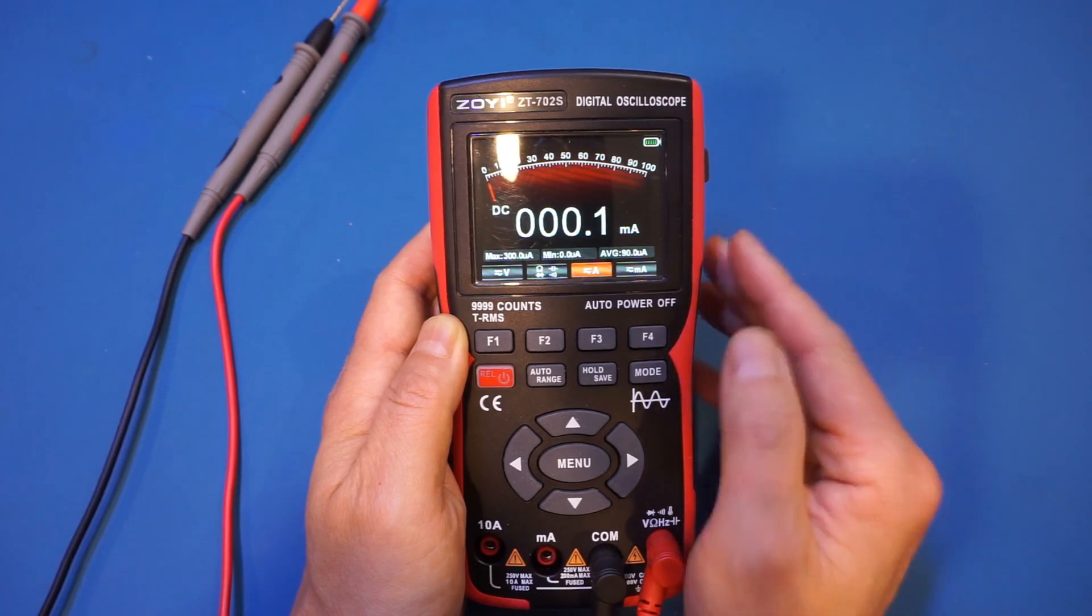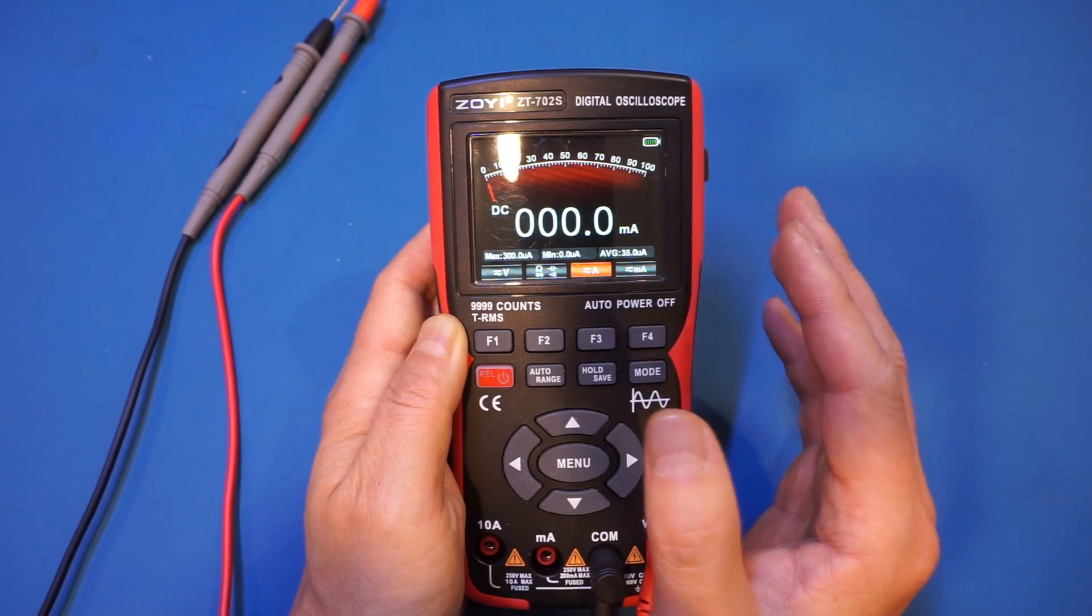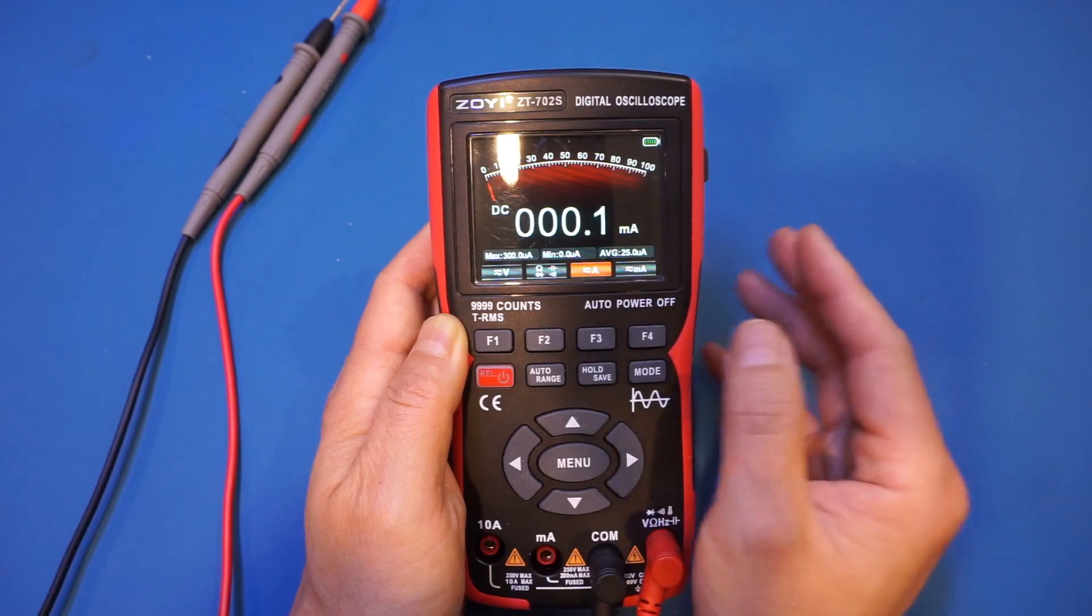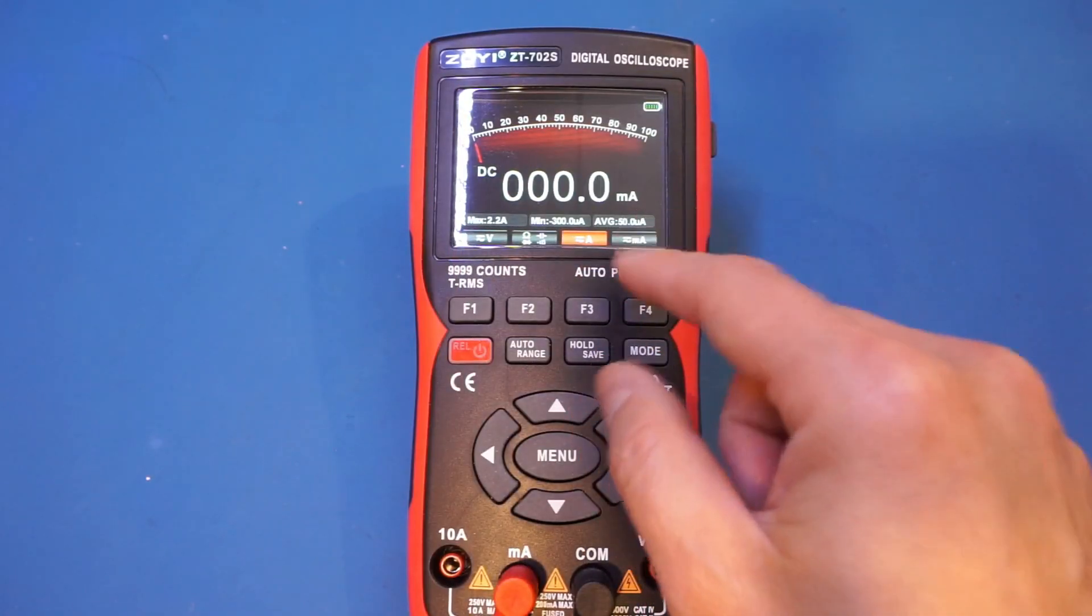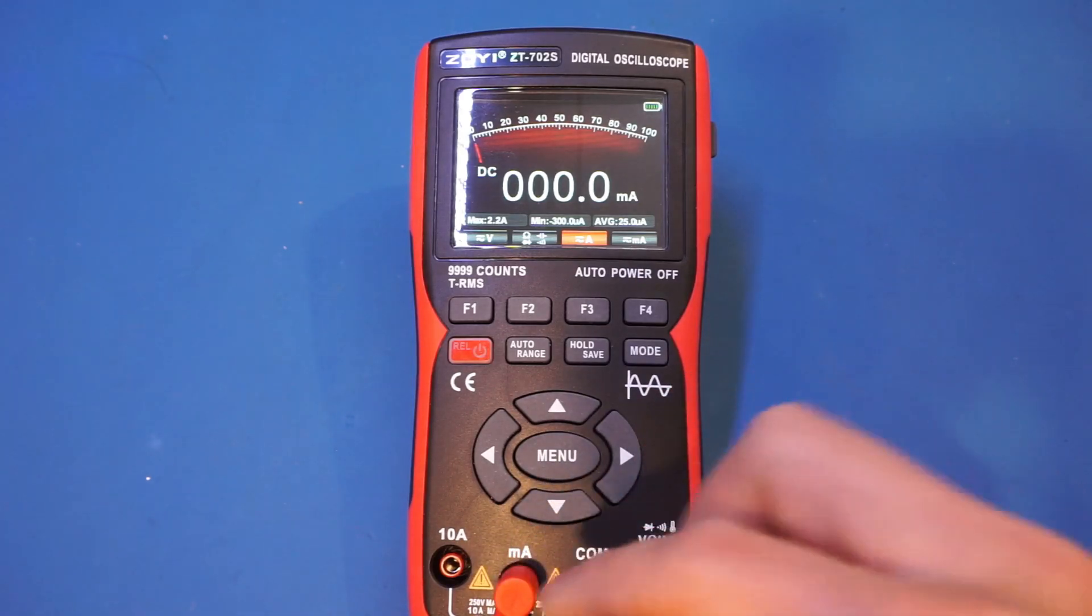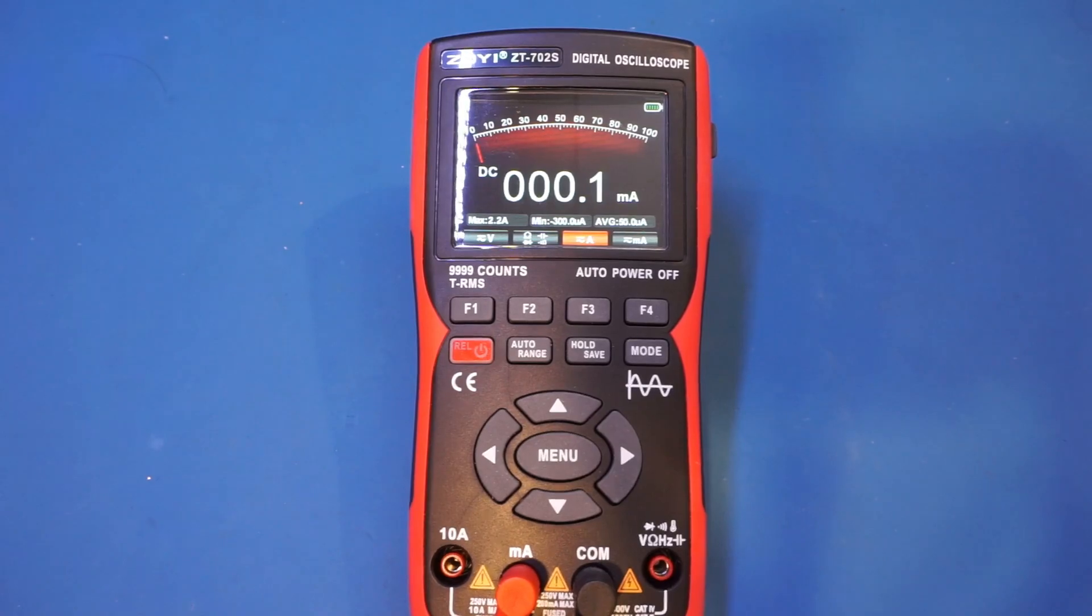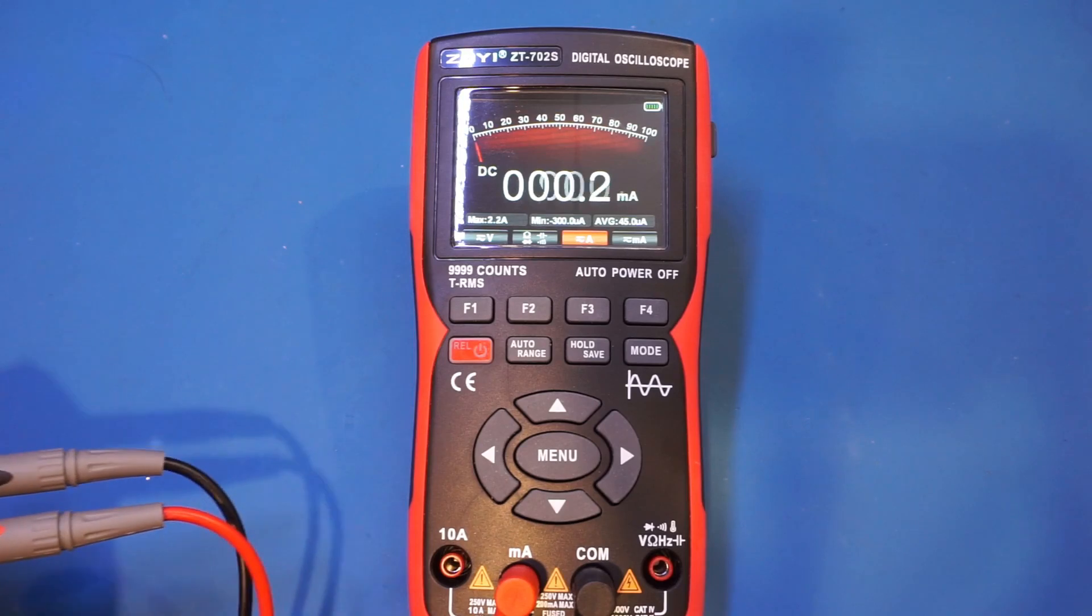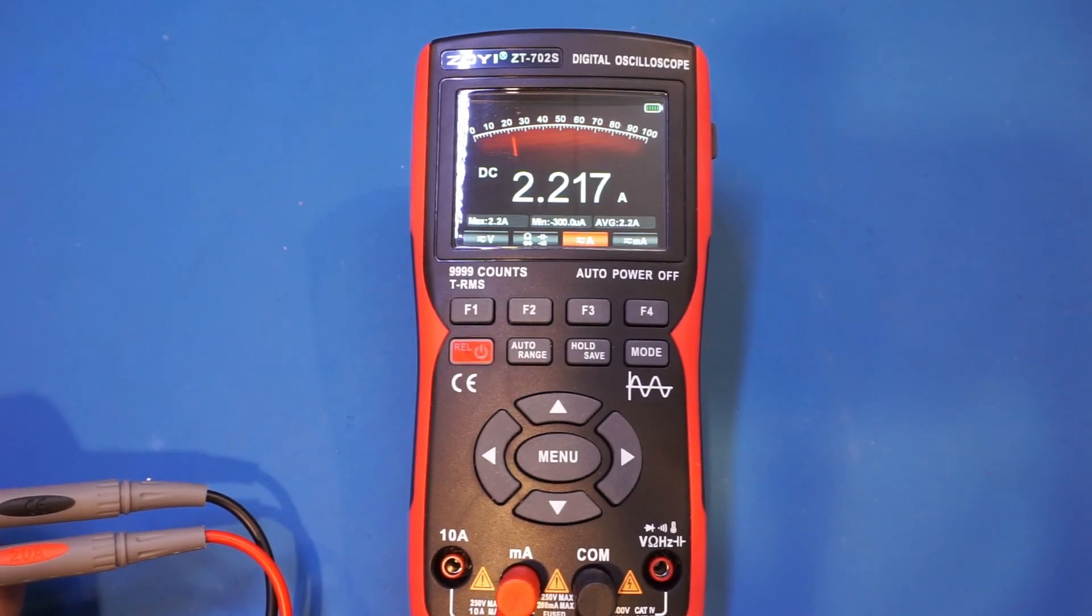So that was actually part of the problem, as a user who intends to measure a milliamp range might not notice that it requires one extra button push and proceeds to the measurement directly. Now let's do the measurement. You can see we're currently in the wrong range for the input jacks. We're in the milliamp range, but the measurement is actually in the amp range. Remember, we have a 20 milliamp current source here. So if you see, we're actually reading 2 amps. That is clearly inaccurate.